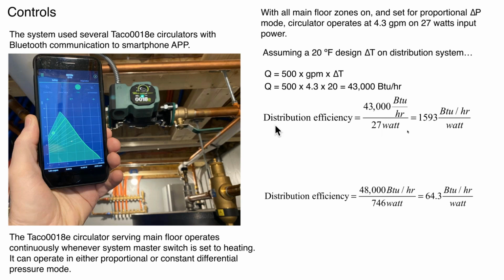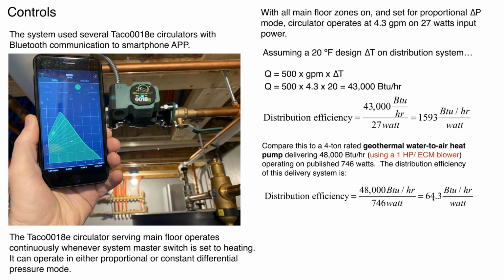So last week we talked about distribution efficiency. It's just the rate of heat delivery divided by the necessary electrical wattage to run the distribution system. So we get this number, almost 1,600 BTUs per hour being delivered from the mechanical room to where it's needed per watt. And I just compared it to, let's say, a blower. It could be a water to air heat pump, or it could be a furnace. Let's say we're delivering 48,000 BTUs per hour, and the blower motor needs 746 watts. We have a much lower distribution efficiency, okay?